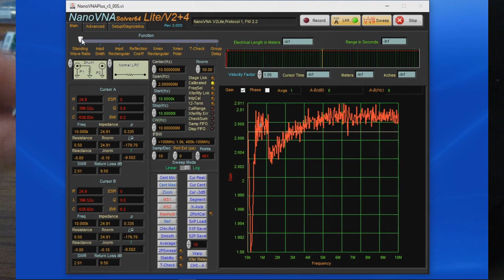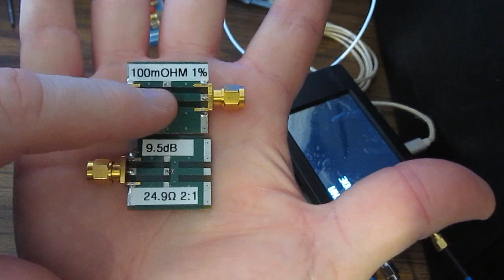Again, as we start looking at lower value resistors, we're going to change from the shunt configuration to the shunt through. So again, this resistor is essentially from the center conductor to ground, just like what this one is. However, we're going to place this in series between the two ports, and this is where our transformer comes into play. If you're interested in understanding the reason why that is, I suggest you watch that video that I made on the PDN measurements. Alright, so I've changed our start frequency to 30 kilohertz.